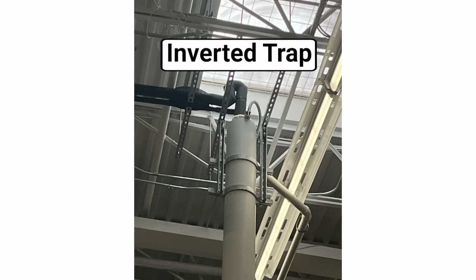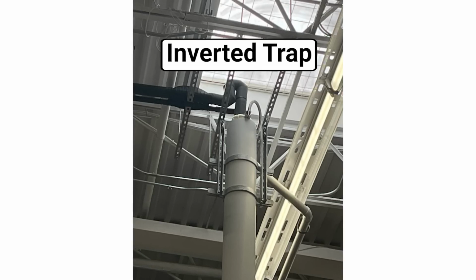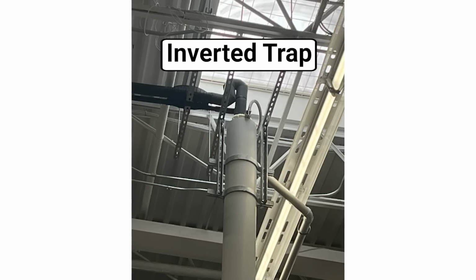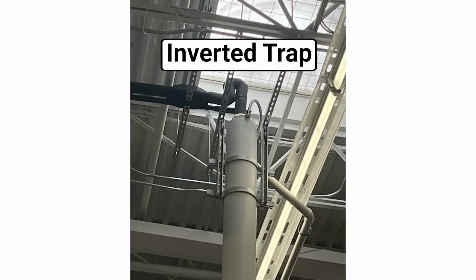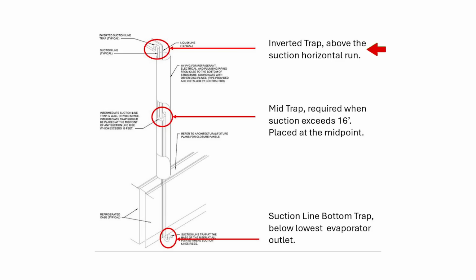In either event, at the top of that, I'm going to want an inverted trap for the exact opposite reason. I don't want the oil to drain into that riser. I just worked so hard to get all the oil up to the top. If I shut that off, I can't risk that oil draining back down that riser, right? So I'm just going to throw an inverted trap. It's an upside down U, if you want to think of it that way. So that suction line, that horizontal run, can't drain back into the riser, right?